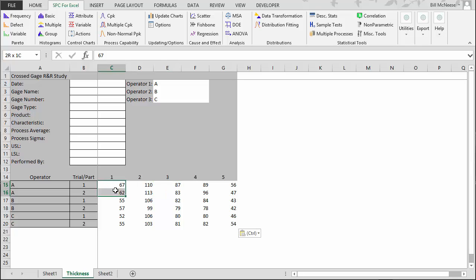One subgroup will be Operator A when he ran part one — the two trials. We'll be calculating the average of the subgroup: the average of 67 and 62 for the X-bar chart, which is 64.5. And then taking a look at the range — in this case, the range is five. We'll be comparing that for all the operator-part combinations.